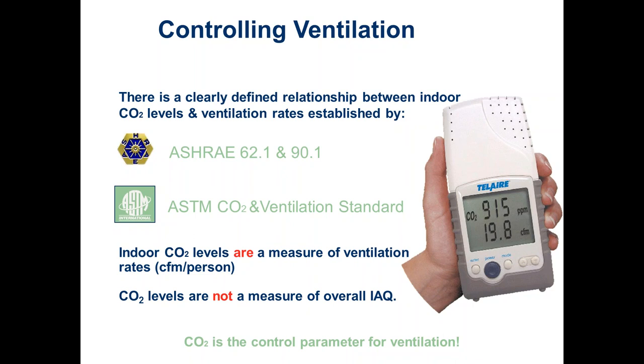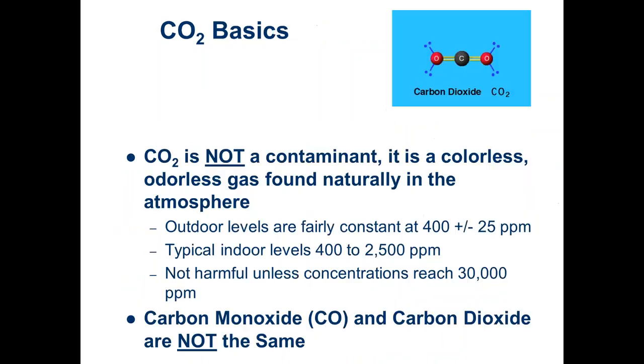ASHRAE 62.1 is our ventilation standard for the country, and the International Mechanical Code piggybacks off that — both have provisions for CO2-based DCV. ASHRAE 90.1 is our energy standard, and the International Energy Conservation Code piggybacks off that; both also have provisions. It's pretty well established that you can use CO2 sensors in people-based occupancies to indicate and adjust the ventilation rate.